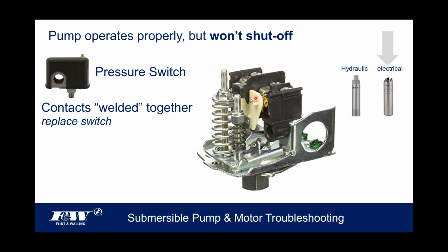If those contacts are welded, back in the day I've had guys tell me, yeah, we'd clean those up, file them back, and whatever. Again, you can do what you want. We've got to make the contacts open and close. Probably the best way for that to happen is to pull that switch off and replace it. At least that's an opinion or an attitude I have about that particular switch.